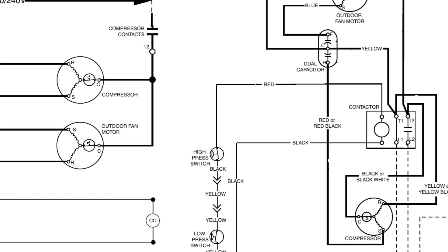Now another place we want to focus in on are anywhere where lines intersect. So on the schematic on the right, you will see that there's lines overlapping. That does not indicate that those lines are connecting. So we don't have high and low voltage wires connecting to one another. In the ladder diagram, you will see circles and these indicate actual connections. So whenever you have overlapping lines with nothing there, they do not connect. And whenever you have these circles, those are wires that actually do connect.